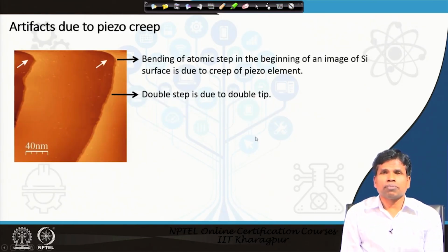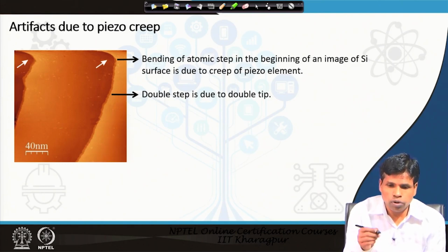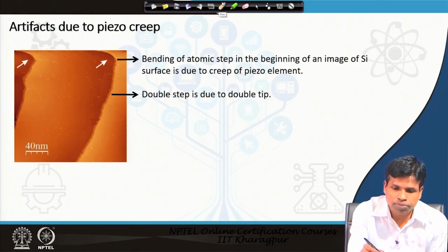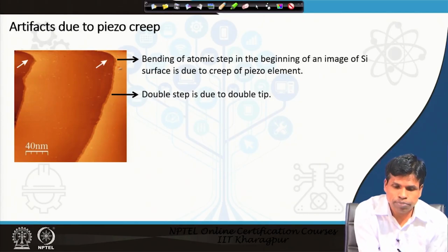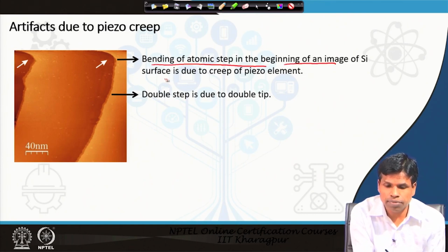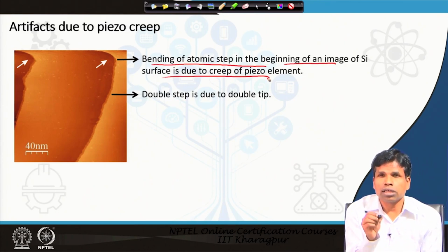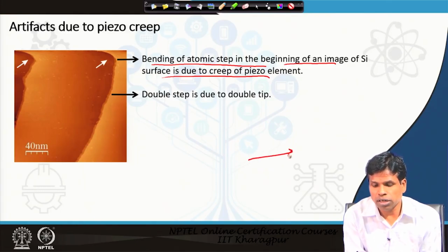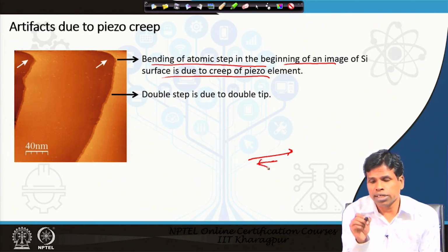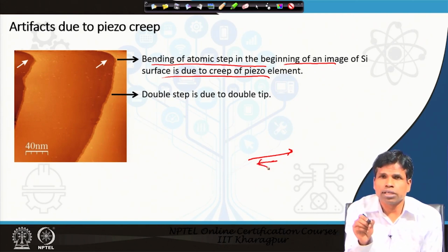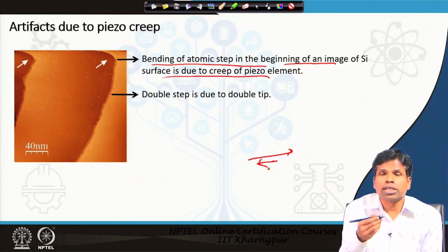Artifacts can also be due to the piezoelectric scanner, particularly due to creep and non-linearity, and we have discussed before what creep is. It is a time dependent phenomenon. Normally here you see there is a bending of the steps in the beginning of the image due to creep of the piezoelectric effect. To the piezoelectric scanner we provide a voltage, and when we provide the voltage, it will expand or contract. Now, if we are applying a positive potential, the tip has to move, expanding, and when we bring back the voltage, the tip should contract quickly, but it cannot.